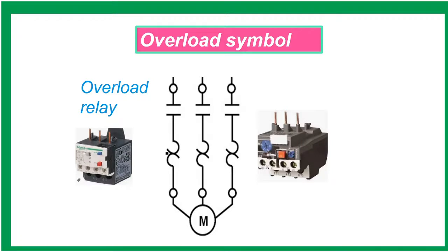Thermal overload relay is designed to protect the motor in case of phase failure or overload. The thermal overload relay does not directly shut down the load. Instead, it triggers one or several auxiliary contacts which then disconnect the motor.